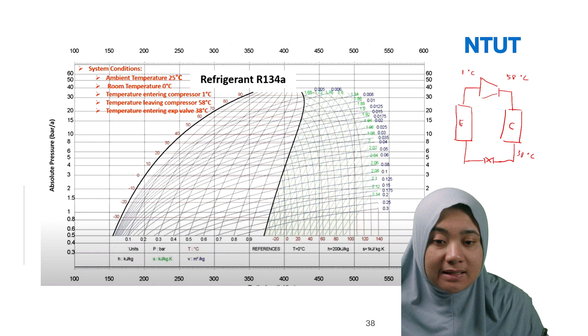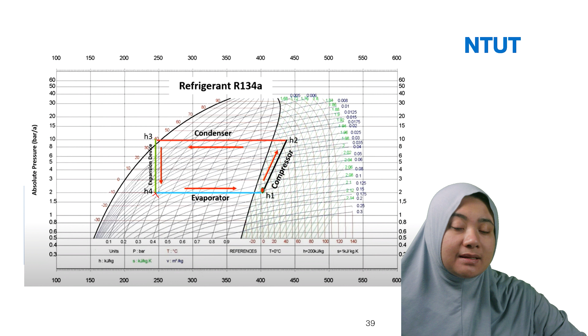For example, the temperature entering the compressor is 1 degree C. So it means you can adjust that it should be at 1 degree C entering the compressor, and then leaving at 58 degrees C for the compressor leave. So when the compressor leaves, it is actually entering the condenser, and then it is reduced to 38 degrees C for the expansion valve. So this is one example of how we read the refrigeration R134A.